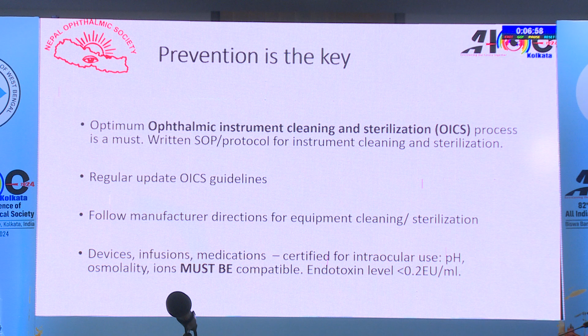While sterilizing and cleaning, there should be adequate flushing of the hollow devices. We should not allow them to dry. We should always keep them moist, and clean them with distilled water, air, distilled water, air, distilled water till dry.